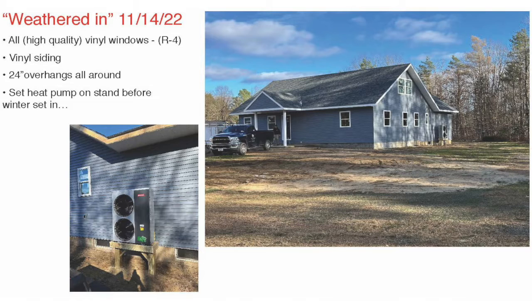24-inch overhangs all around. You can see the heat pump in the upper right corner there. My laser is not really working here, but if you look on the right side of the house, you'll see the heat pump. It's very similar to the heat pump that's over here. It's up on a stand. You can see the stand there in the lower left. It's a pressure-treated stand. It was designed to keep the unit up above the snow. You don't want to set these heat pumps on the ground or 2 or 3 or 4 inches above the ground for a couple reasons.